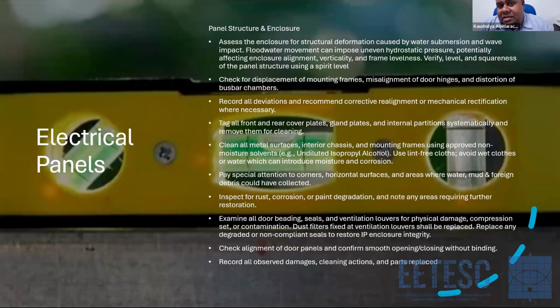Panels and enclosures. Assess the enclosure for structural deformation. If any structural deformation is present, that's going to be very difficult, and that's going to be costly. If the structural deformation is minor, you may be able to replace some of the structural parts. If that is major, you will have to think of a new switchgear enclosure, a panel.